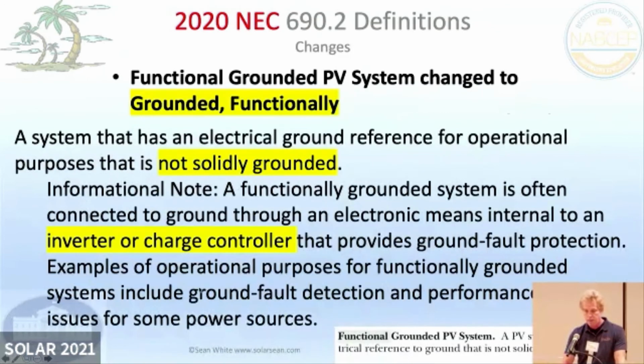Electronic power converter. What they did that was a big change in the 2017 NEC is they changed the way they talked about grounding. In the 2014 NEC and earlier, we always talked about grounded and ungrounded inverters. They changed it. Now the ones that we used to call grounded, that were fuse grounded, that were not solidly grounded, we don't really even use that kind except for utility scale systems. And now they're not even called grounded. They're called functionally grounded. They figured out the ones that we used to call grounded were only functionally grounded. And the ones that we used to call ungrounded really were a little bit grounded. So they are functionally grounded, because the inverters that we use, the transformerless inverters, formerly known as ungrounded inverters, almost everything you use, unless you're doing a big utility scale system, is like that.